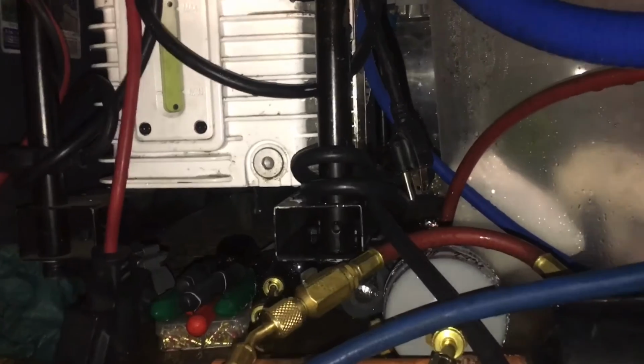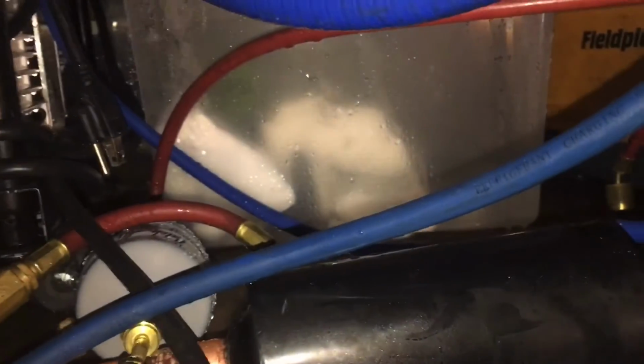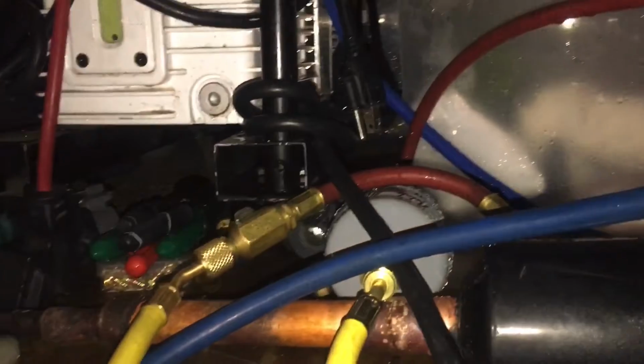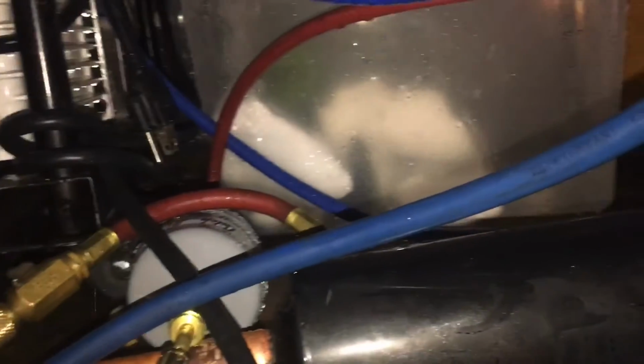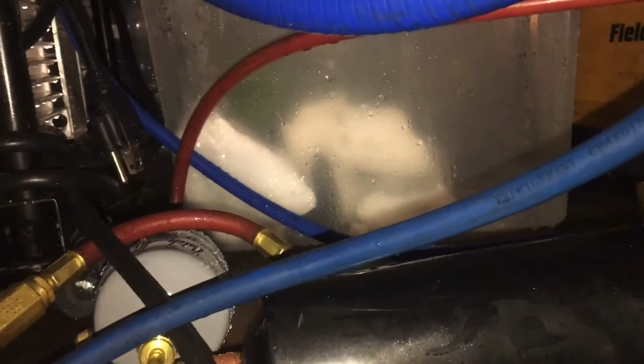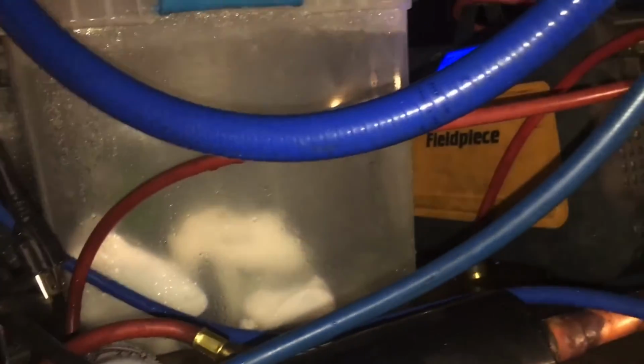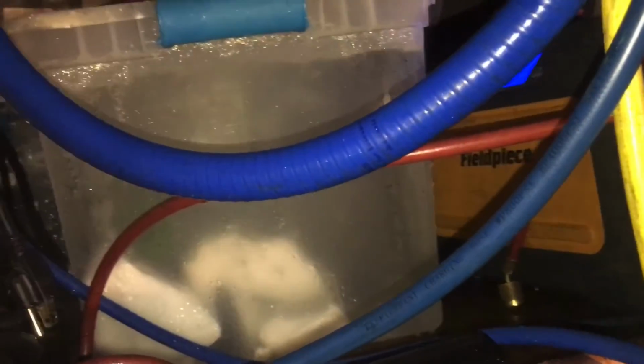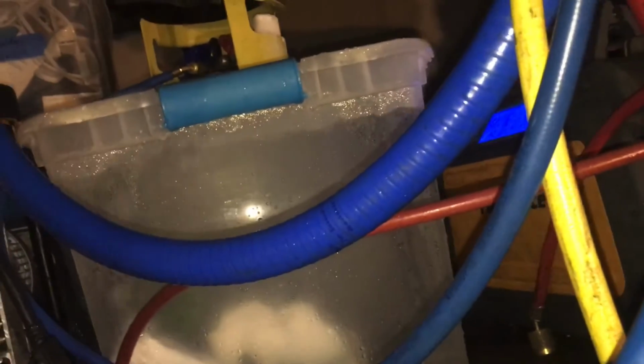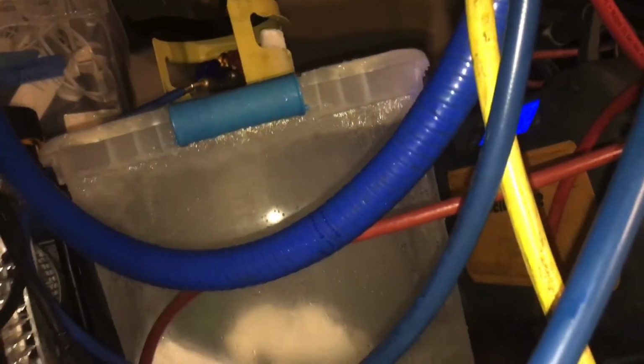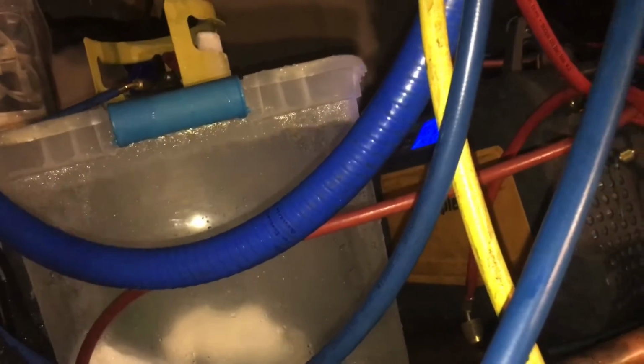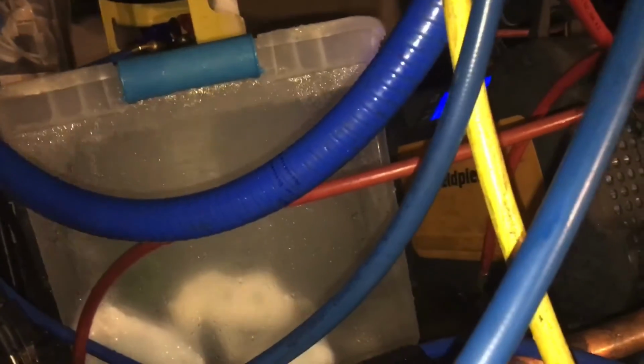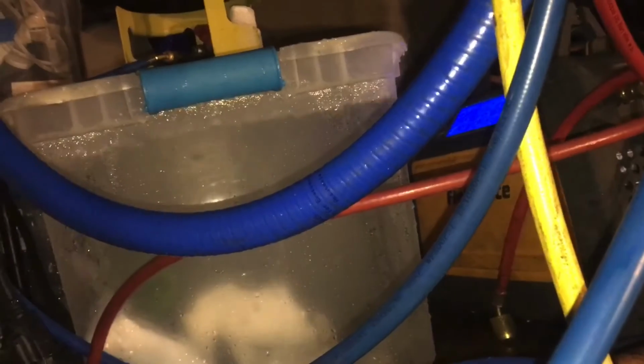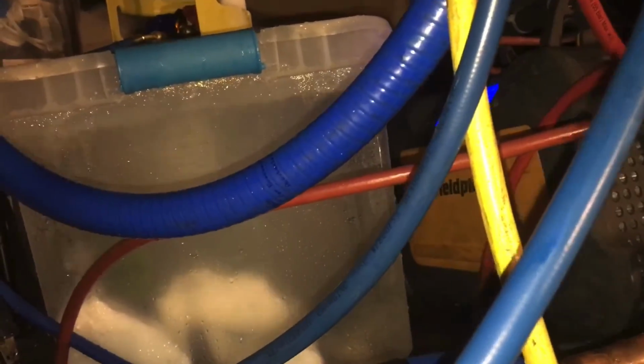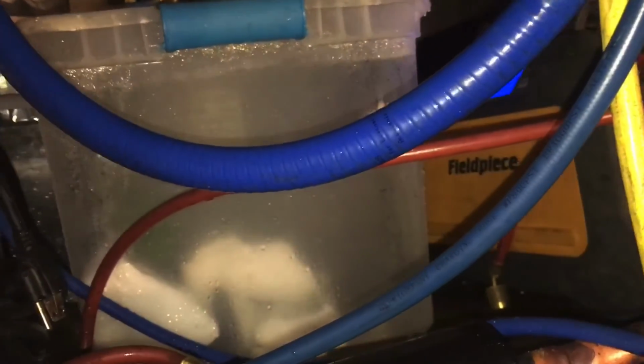And if I didn't tell you already, because I'm doing this ad lib and I'm not doing any editing, we had 9 air handlers that were completely blocked with barely any airflow. We had 1 air handler with a dead fan motor in it. Outside temperatures were between the 40s and 50s degrees.